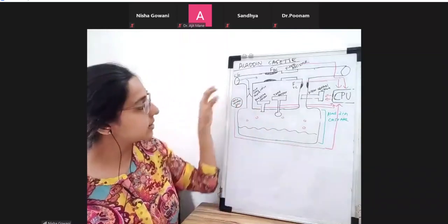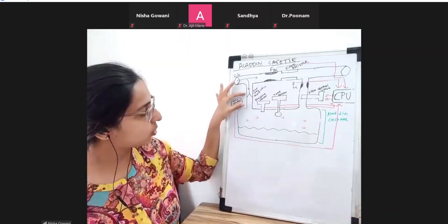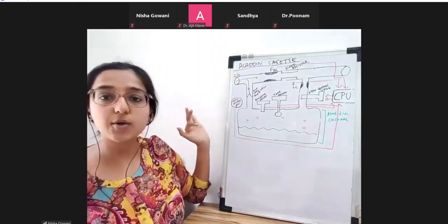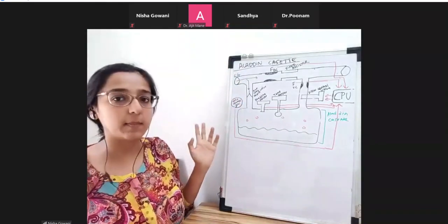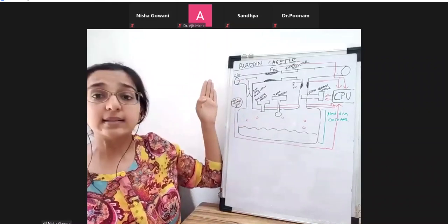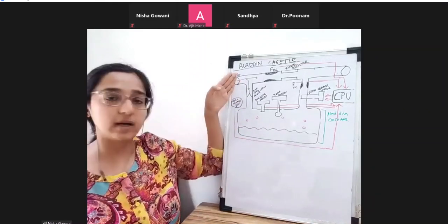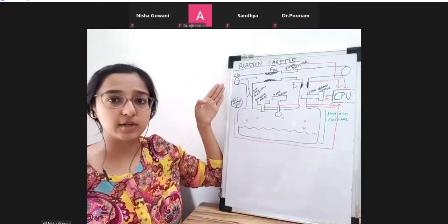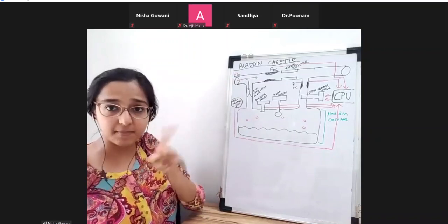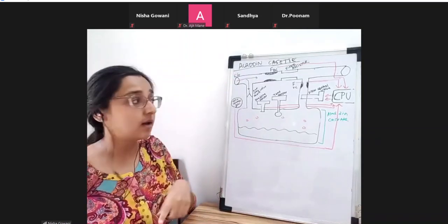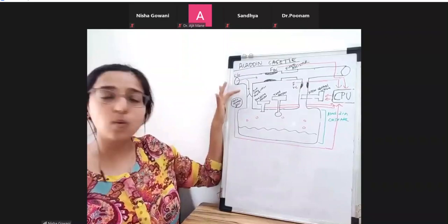There is also a one-way check valve that I've drawn over here. You remember there was a problem in the variable bypass vaporizer: there was a chance of retrograde flow of the vapor-laden gas, which we did not want. So a spiral labyrinth was added there. Here that is not there. Here there is a one-way check valve.